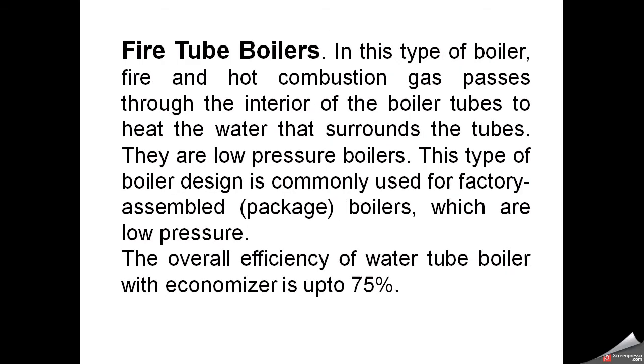Fire tube boiler is based on design classification. In this type of boiler, fire and hot combustion gases pass through the interior of the boiler tubes to heat the water that surrounds the tubes in a tank. Fire tube boilers are low pressure boilers commonly used for factory assembled boilers. The overall efficiency with economizer is up to 75%.